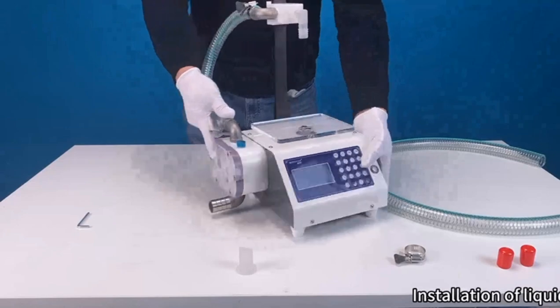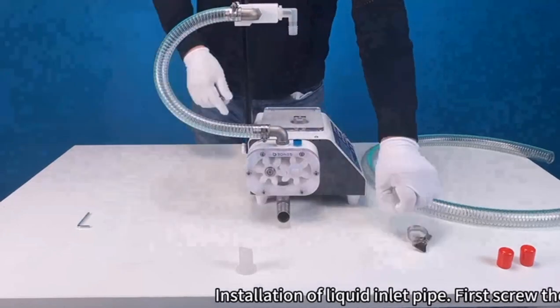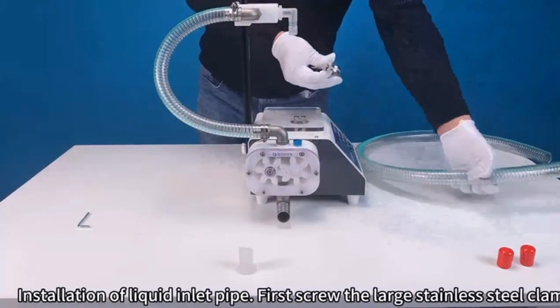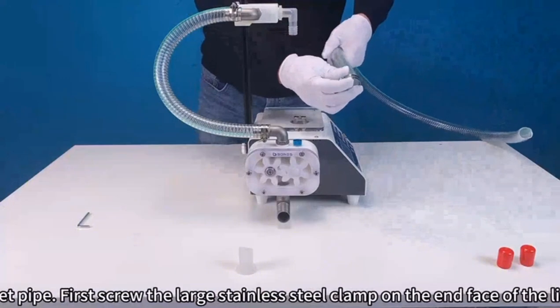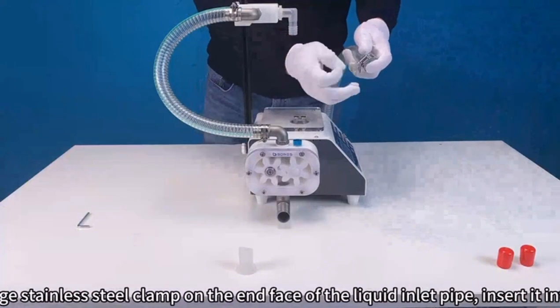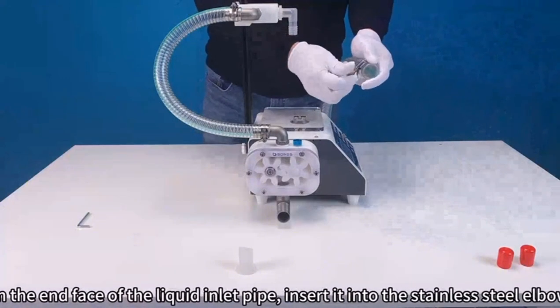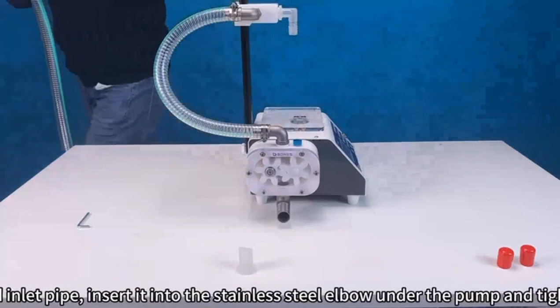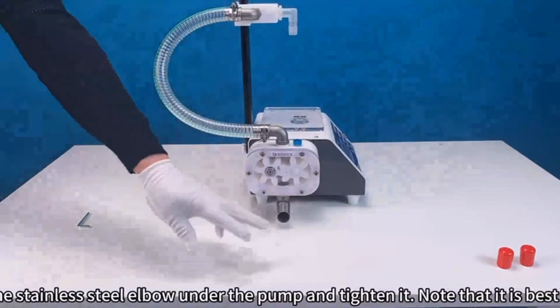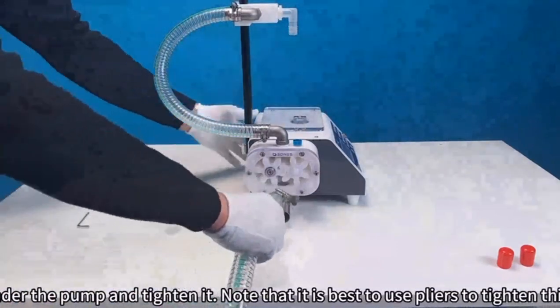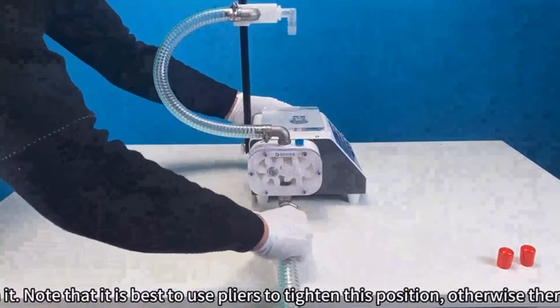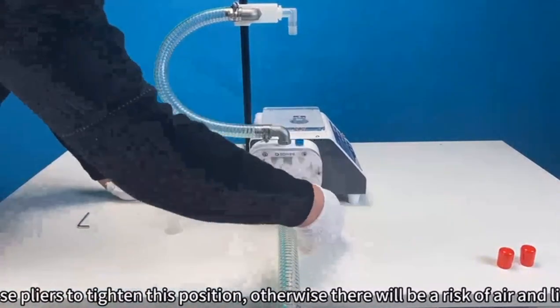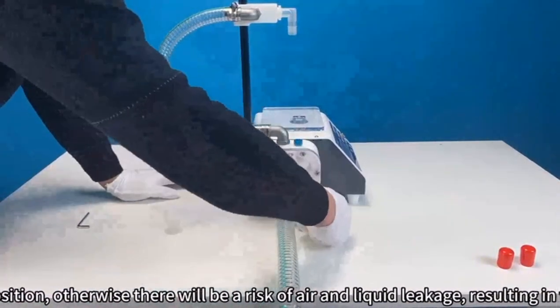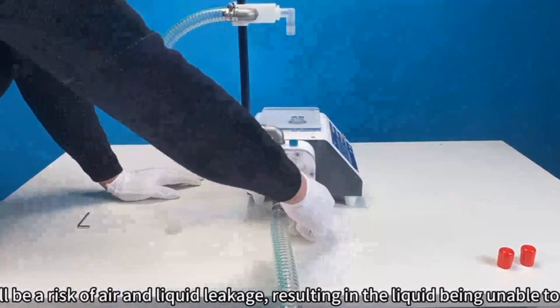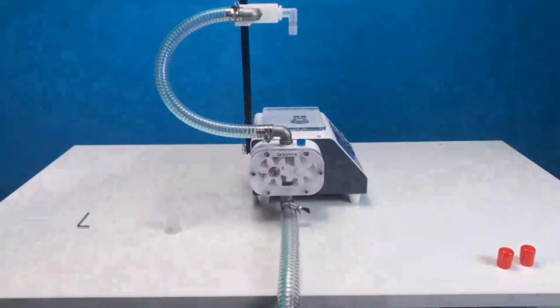Installation of liquid inlet pipe. First screw the large stainless steel clamp on the end face of the liquid inlet pipe. Insert it into the stainless steel elbow under the pump and tighten it. Note that it is best to use pliers to tighten this position, otherwise there will be a risk of air and liquid leakage, resulting in the liquid being unable to be pumped out.